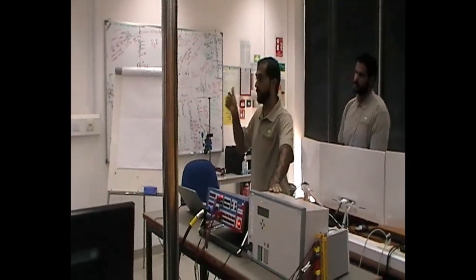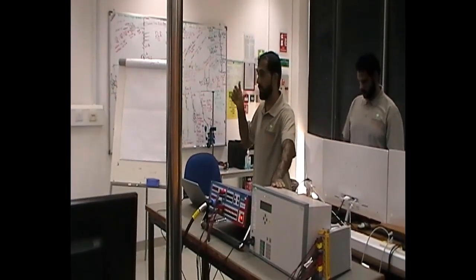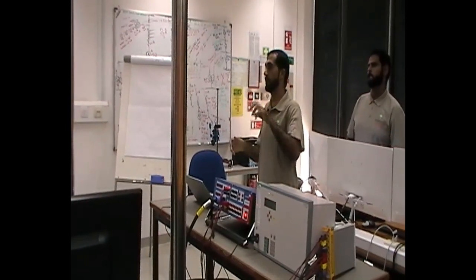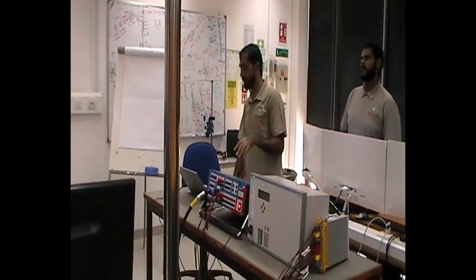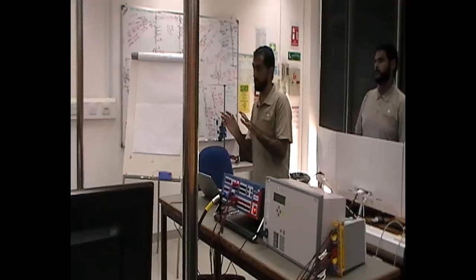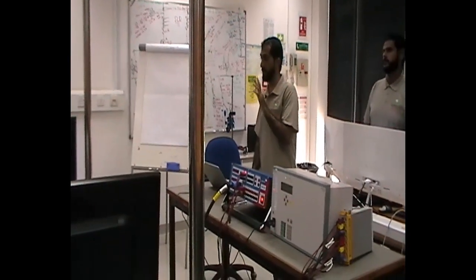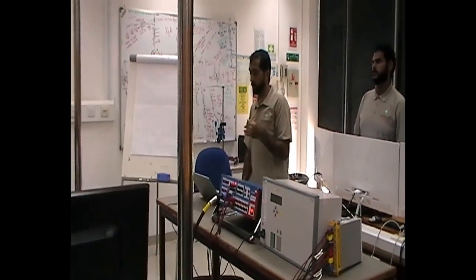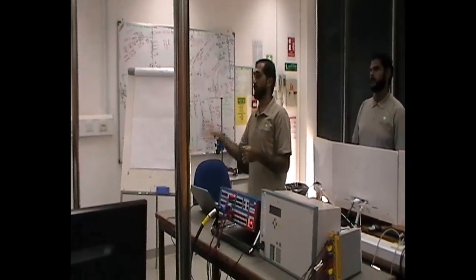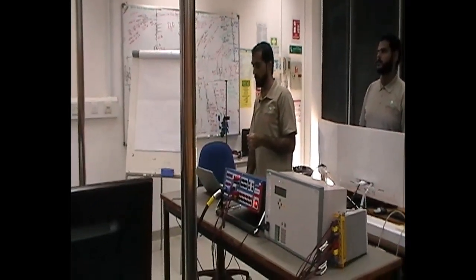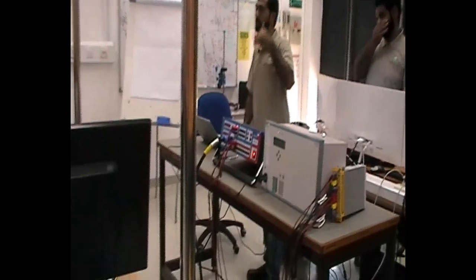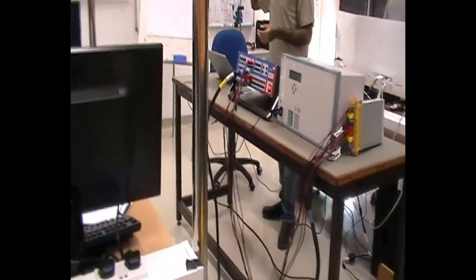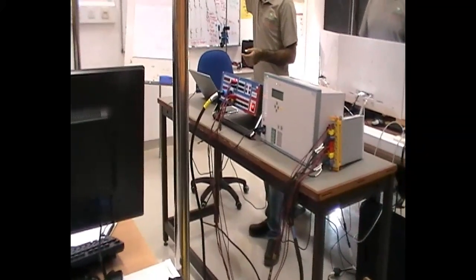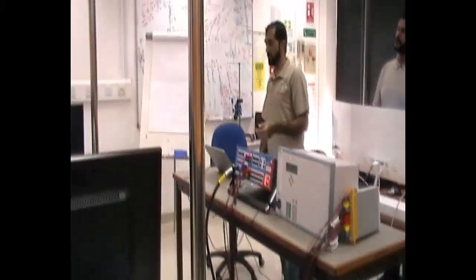So zone 1 is 85% of the line impedance, because I'm sure the fault is in the line. That's why I'm tripping in no time, like 0 milliseconds. But zone 2 and zone 3 go beyond the line. Zone 2 will usually cover a little bit more, like 120% of the line. So I need to give some time for whatever protection inside that remote substation to operate. So I'm giving it 100 milliseconds.